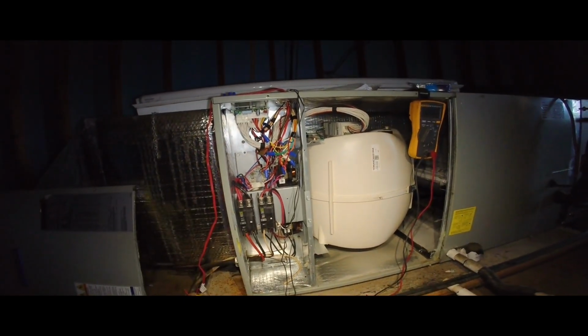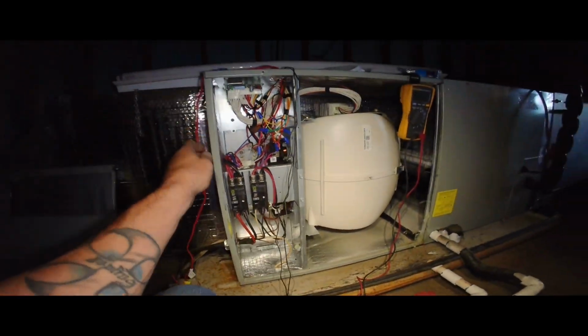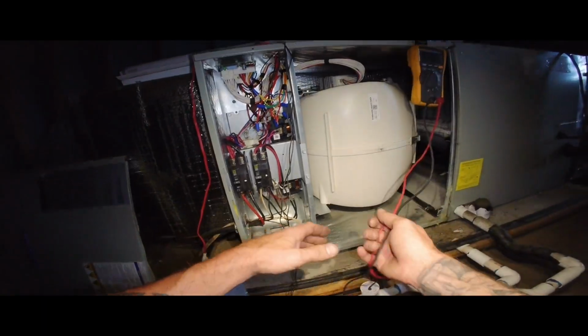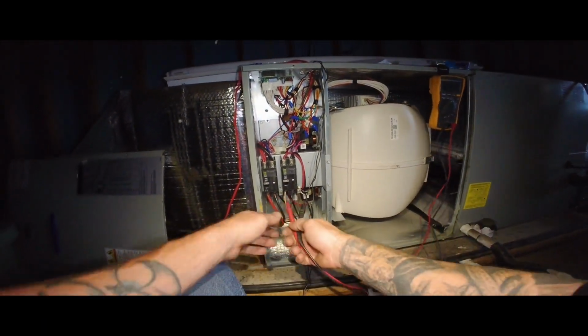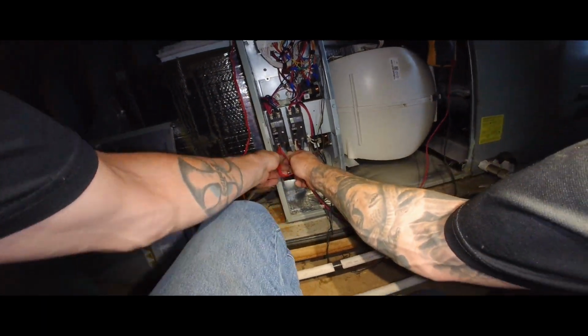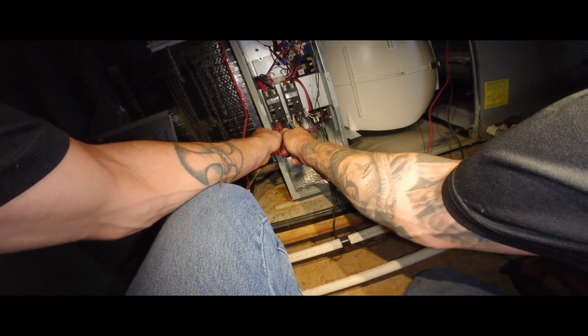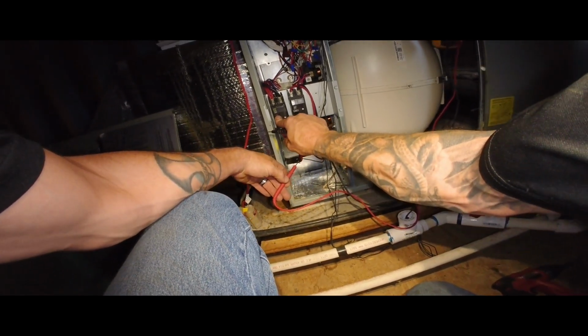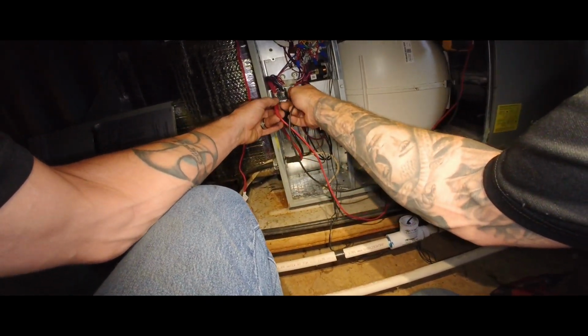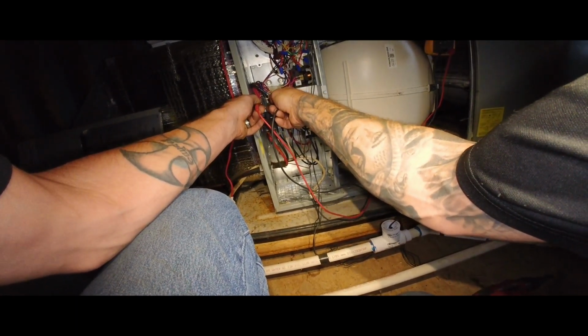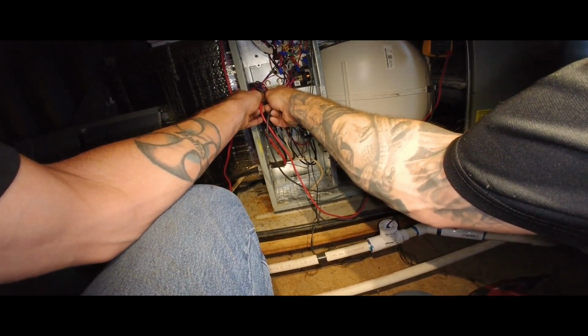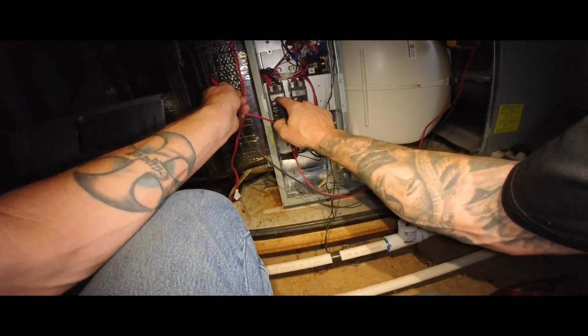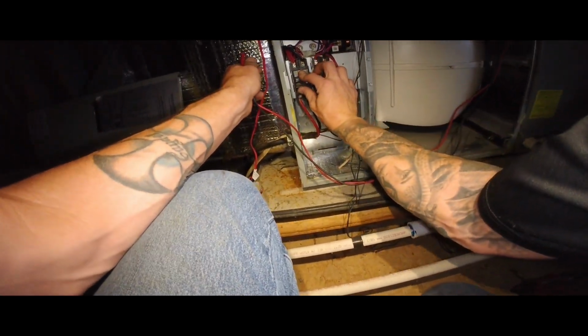The fuse is good. So next order of business, we take our voltmeter, go down here on these two bottom terminals - 240 volts. Switch it on just to verify the breaker is working. 240 volts.